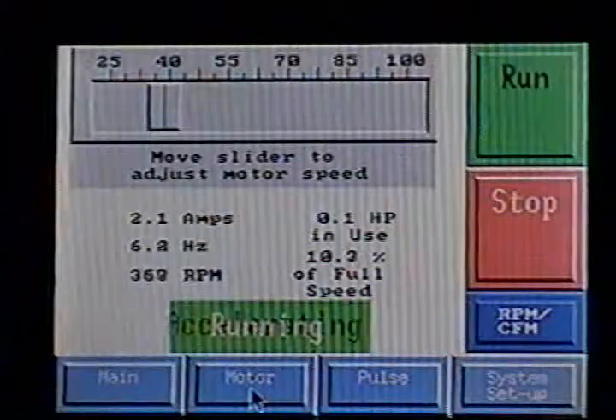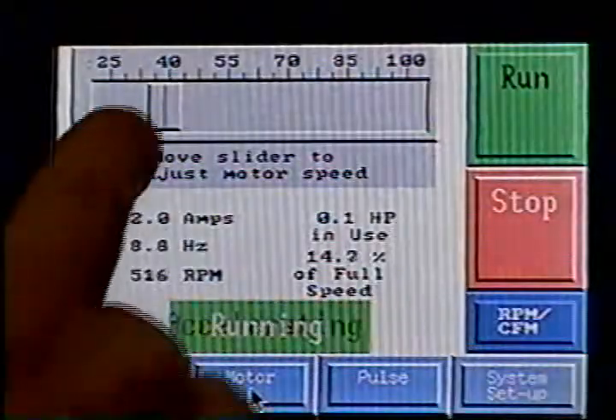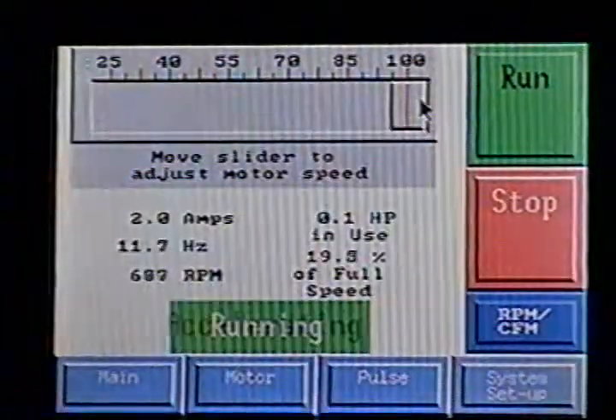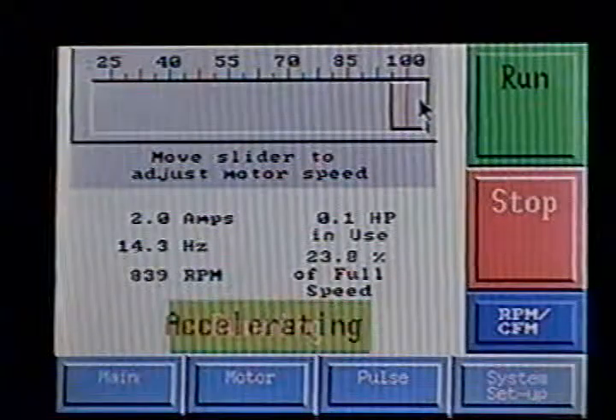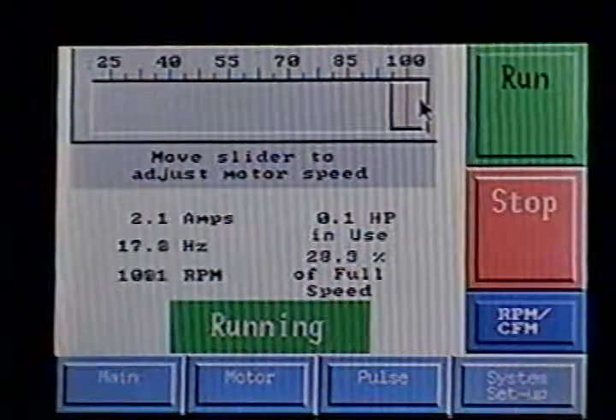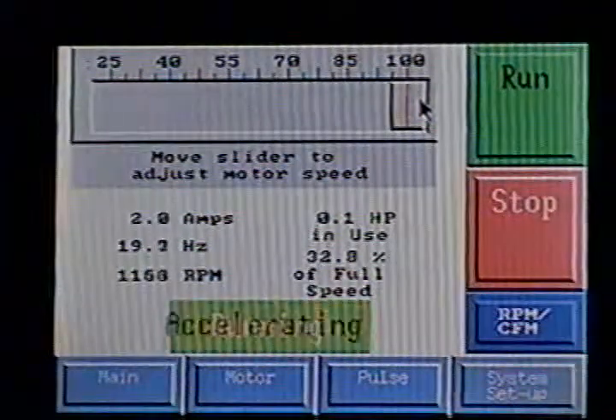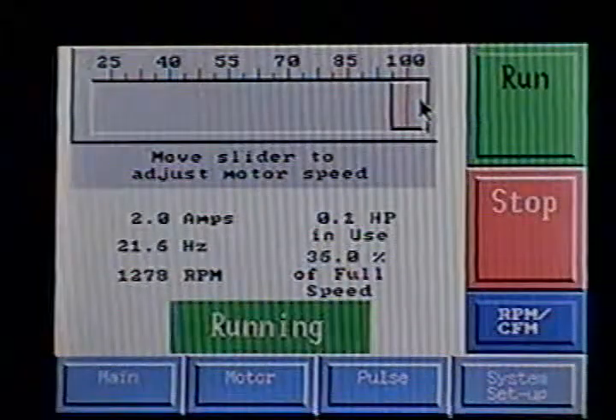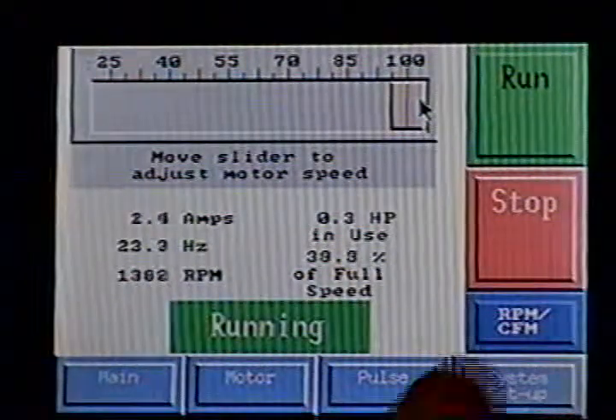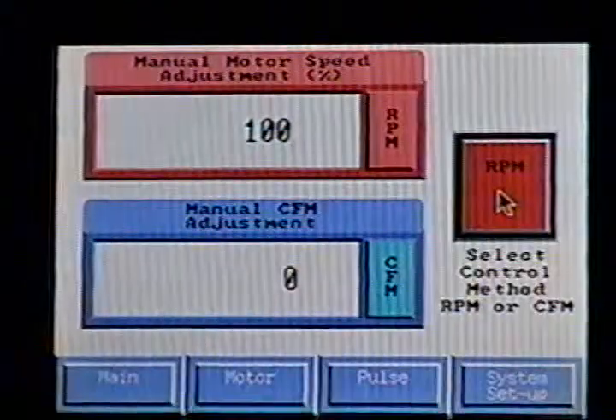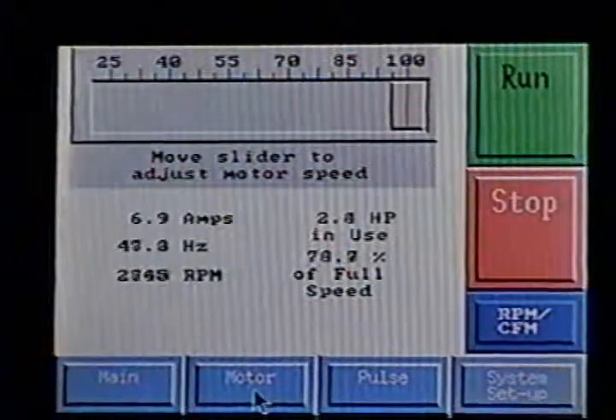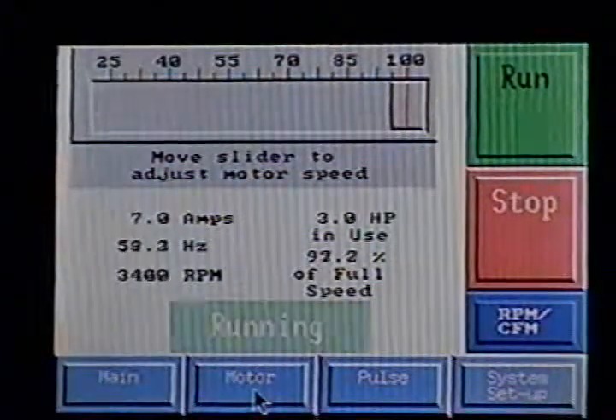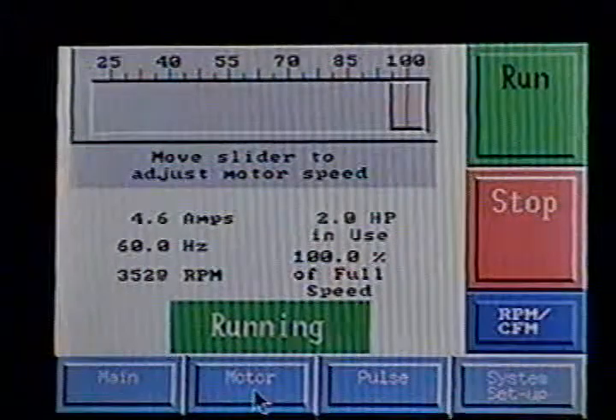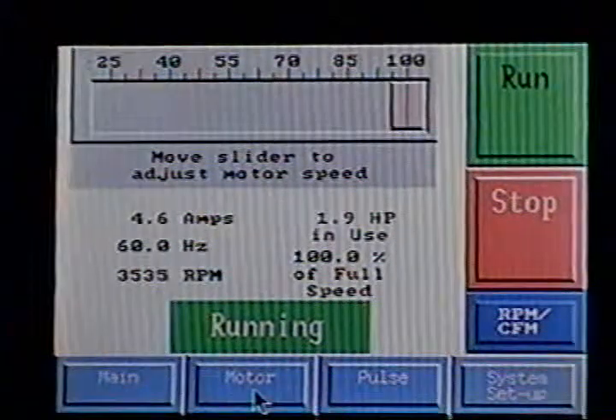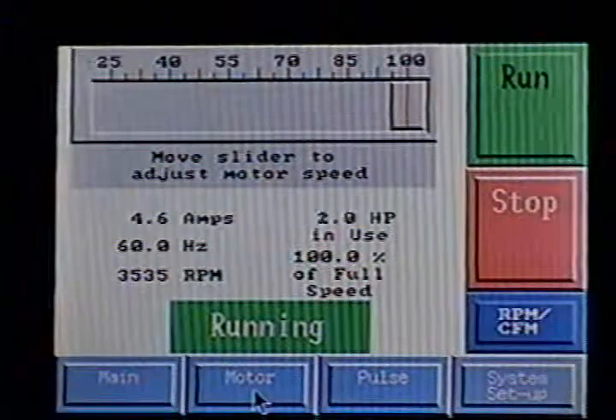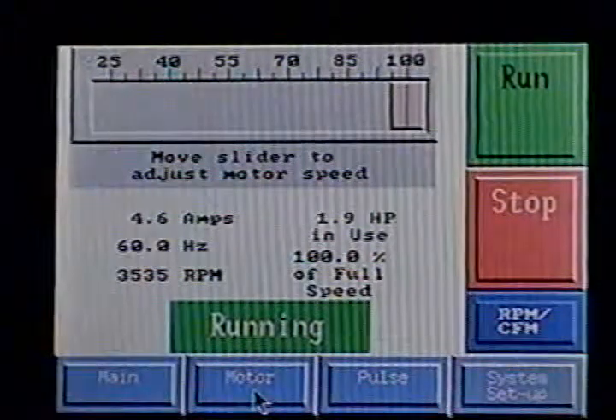Go over here to the motor. You can hear the pulsing take off. It's set at 40%. I'm going to turn it up to 100%. I told you it was a slow start. It doesn't spike your electrical. It's running up to speed now. It's going up. It's currently running at 100% of the full RPM of the motor.